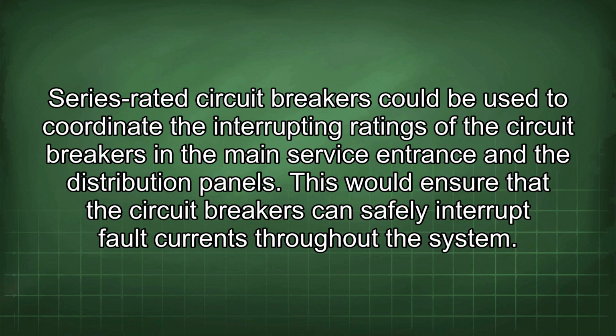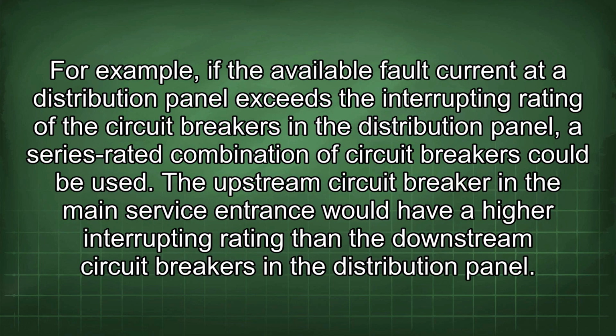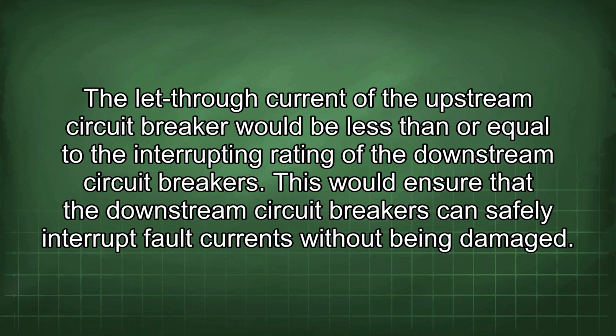Series-rated circuit breakers could be used to coordinate the interrupting ratings of the circuit breakers in the main service entrance and the distribution panels. This would ensure that the circuit breakers can safely interrupt fault currents throughout the system. For example, if the available fault current at a distribution panel exceeds the interrupting rating of the circuit breakers in the distribution panel, a series-rated combination of circuit breakers could be used. The upstream circuit breaker in the main service entrance would have a higher interrupting rating than the downstream circuit breakers in the distribution panel. The let-through current of the upstream circuit breaker would be less than or equal to the interrupting rating of the downstream circuit breakers. This would ensure that the downstream circuit breakers can safely interrupt fault currents without being damaged.